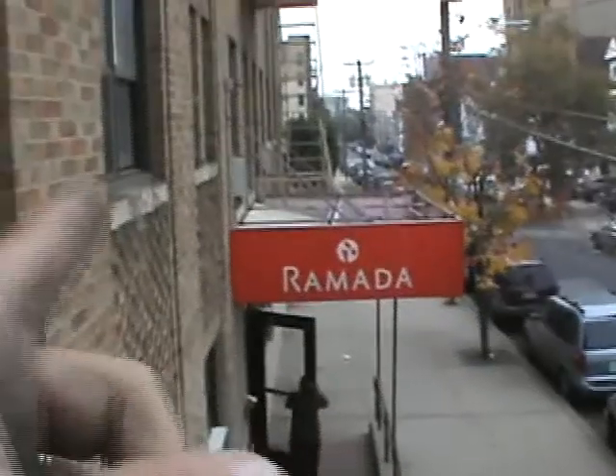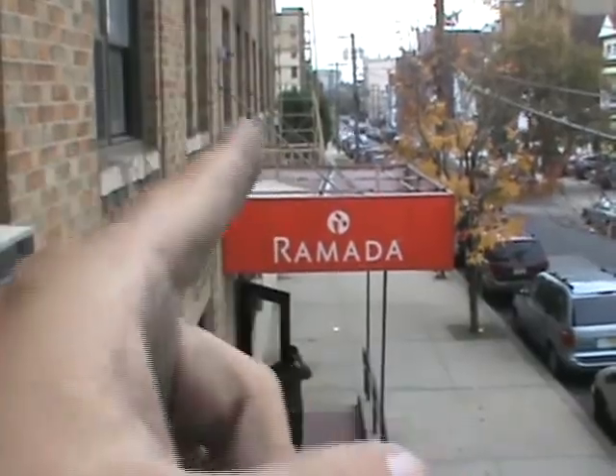And as you can see, because of the way that this fire escape ladder is pivoted, which doesn't have any release arm, that one is a smaller version of the same thing, but that's illegal there. This is illegal because when I drop this out, because of how long it is, she'll get to the ground, but should there be a fireman or anybody down below, and this thing comes down, it'll conk them on the head and either kill them or maim them. So this must be a drop-down ladder. You can put it here so that it drops 2 to 3 feet per second, hits the ground and stays down. And that's what I recommend, getting it off the front, reconfiguring it over here.